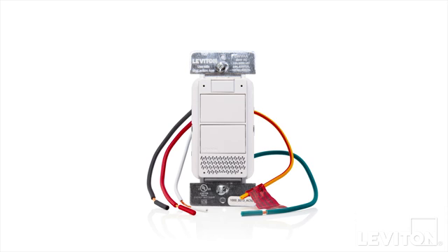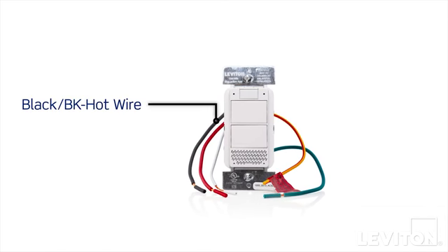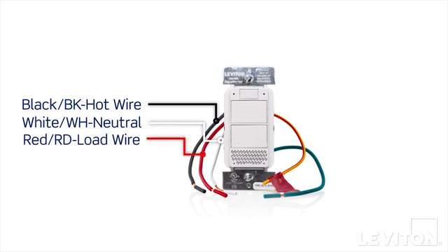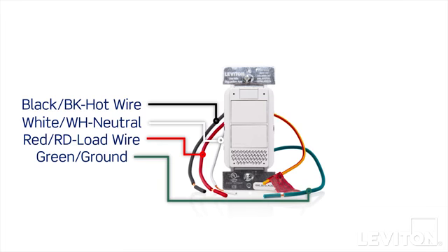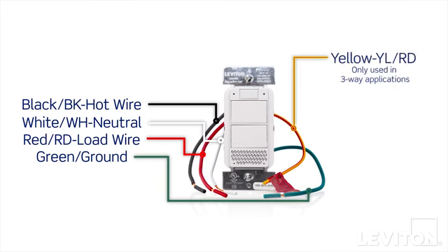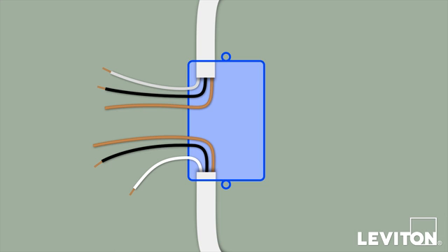Before installing, it's important to identify the wires on your voice dimmer to ensure that you're wiring correctly. The Decora Smart Voice Dimmer includes wire leads to make installation easier. Black or BK is for the line or hot wire. The white wire is for the neutral connection. The red wire is for the load connection, and the green wire is for the ground connection. The yellow wire is only used when wiring in a three-way or multi-way application and is not utilized during single-pole installations.